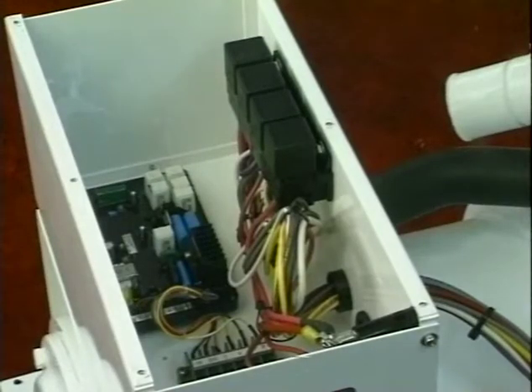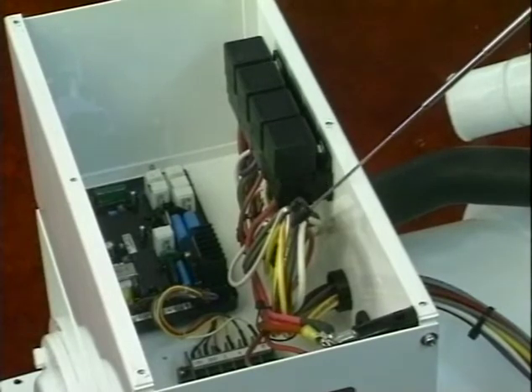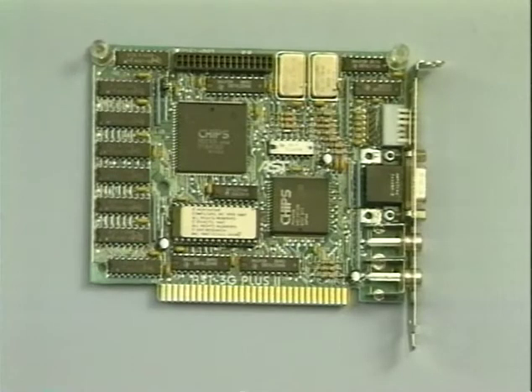That's why every Northern Lights marine set from 5 to 700 kW uses a DC system based on relays and copper wire. Printed circuit boards are fine for non-critical applications. The television you're watching is full of them. We even use them on some of our sophisticated auto-everything industrial generator set switchgear. But for marine applications where the environment is hostile and you can't walk home, we stick with reliable relays. This is true for our Lugger marine propulsion engines as well. Relay logic systems cost more to manufacture, but they dramatically reduce the cost of field service and replacement parts.